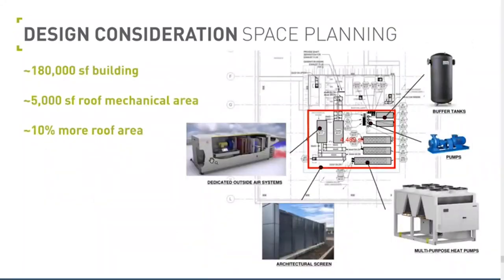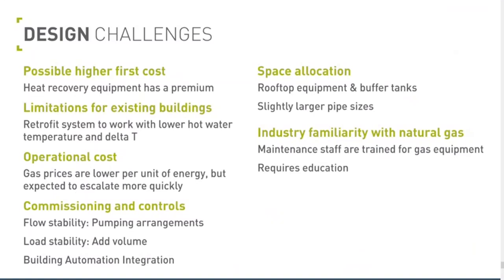Space planning, this is just an example, but this type of system serving about a 200,000 square foot academic building required about 5,000 square feet of mechanical roof area for the air side and the heating systems, the heat pump systems. It takes up more space, right? It's going to take up more of your roof program or site program if it's at grade. And a few minutes left.